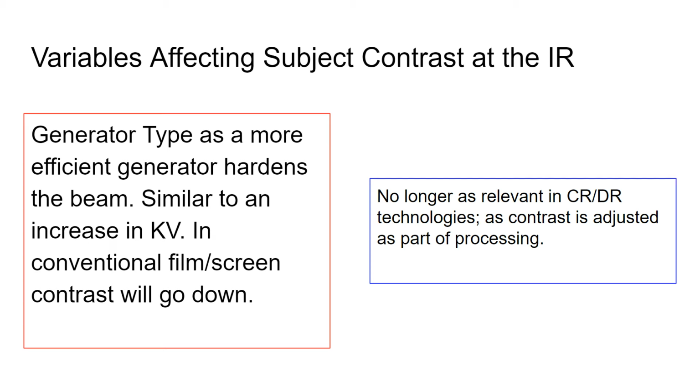With the most high frequency generator out there, you set 100 and you get about 98, 99% of your photons at 100, which means you don't need as much exposure, like we were talking about before, because you have more penetrating x-rays, thus more x-rays in the remnant beam, more x-rays interacting with the image receptor, and more data points for your reconstruction overall.